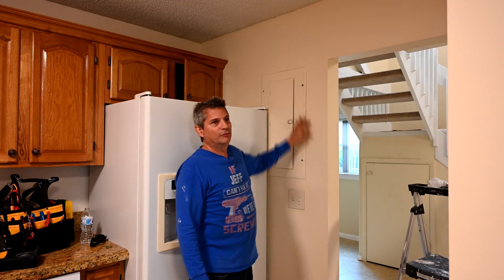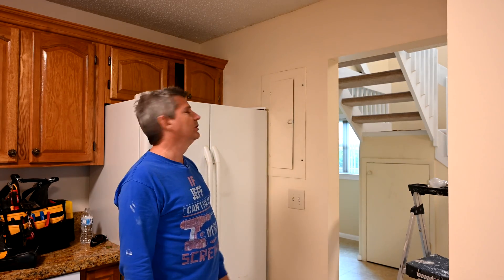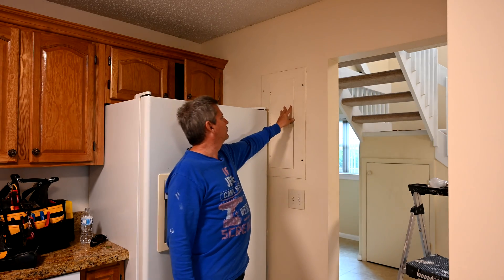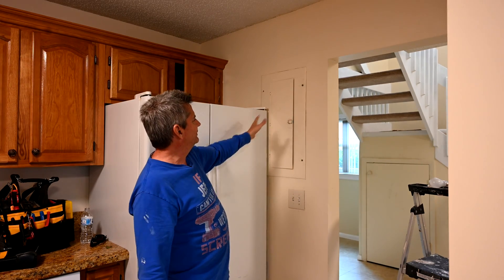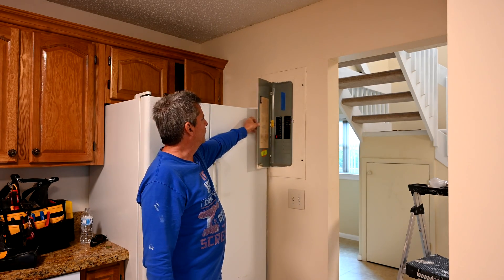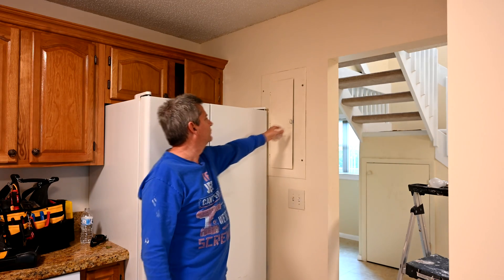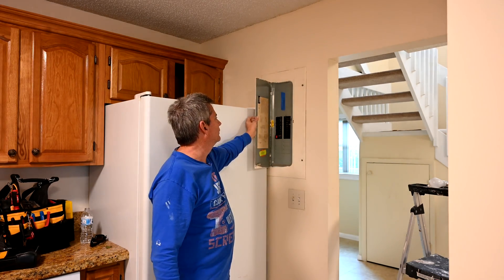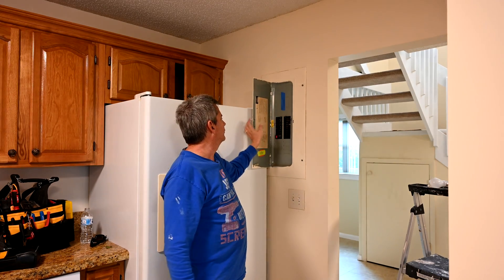As you look at the electrical panel, one of the things you can see is there is a rule in the National Electric Code that requires that you don't block electrical panels. Right now this refrigerator is blocking it — but it's sort of like, is it or isn't it? I mean, you can still open it. The whole purpose of that rule is so that people can get to the fuse door when the lights go out. You can still see you have access to all of your switches here.